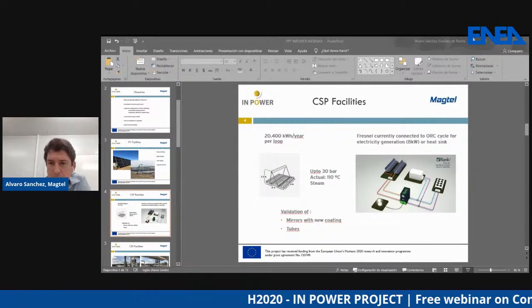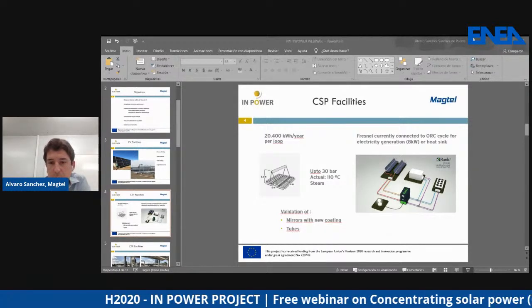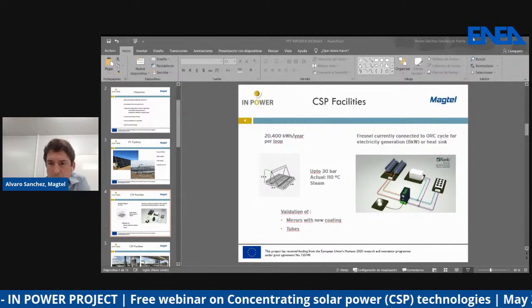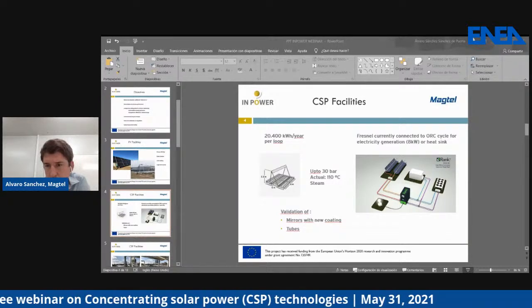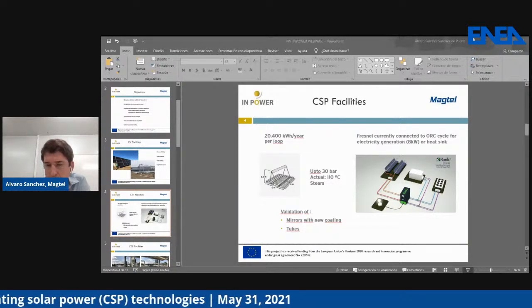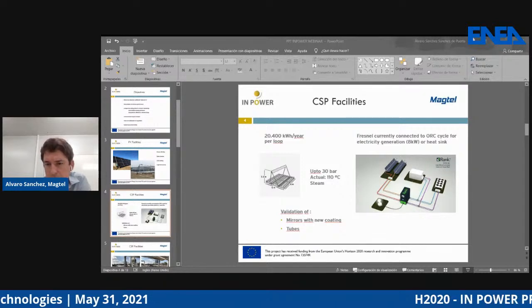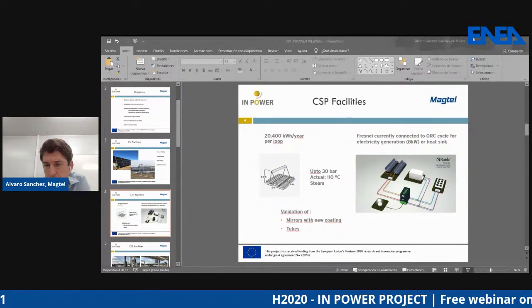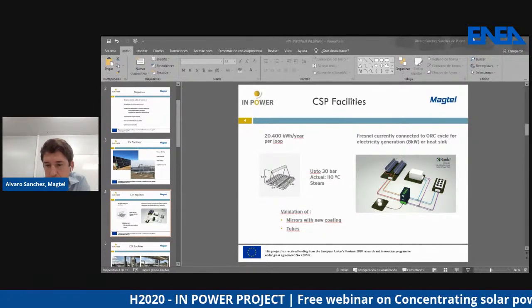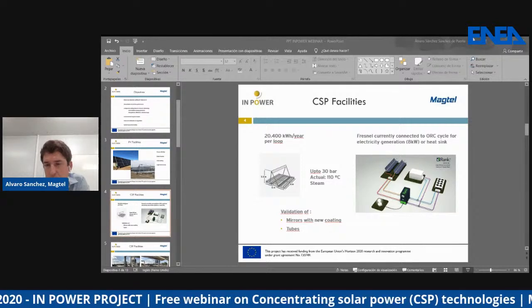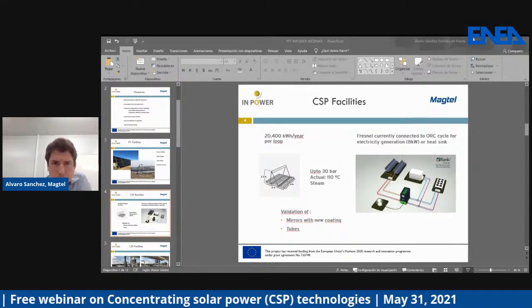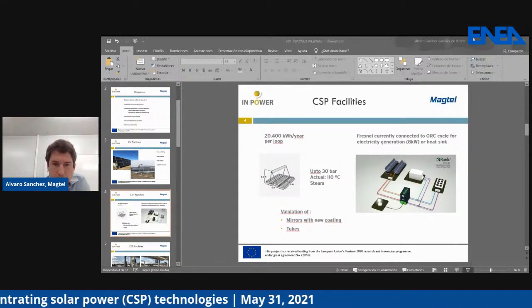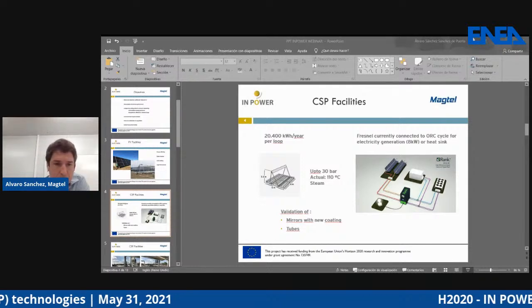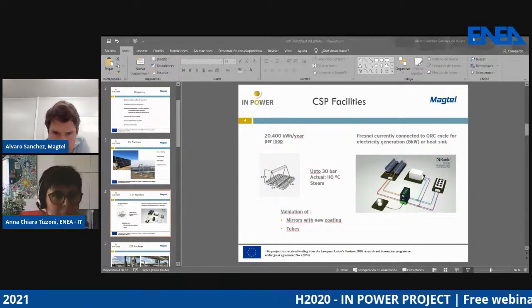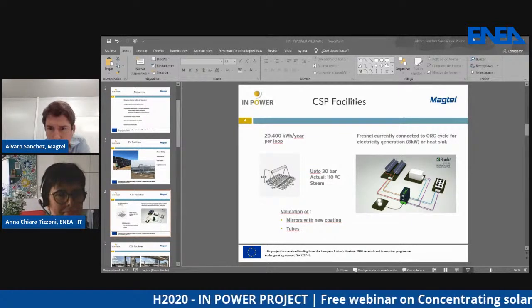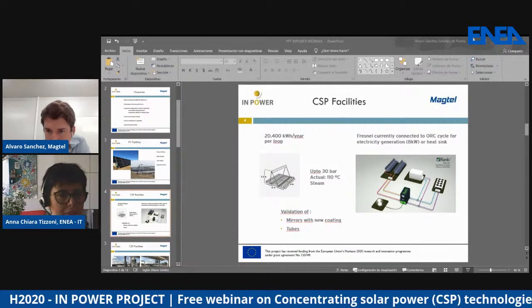So we also have an organic Rankine cycle turbine, or ORC, for production of electricity. As you can see in the loop, there is also a diffuser for excess heat that cannot be absorbed by the ORC, so we can dissipate this heat without causing damage to the circuit. Here you can see a picture of the actual facilities. This is the power block, and this tank is the expansion tank, and also we can see here the diffuser.